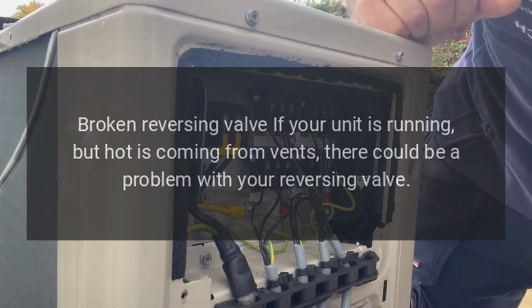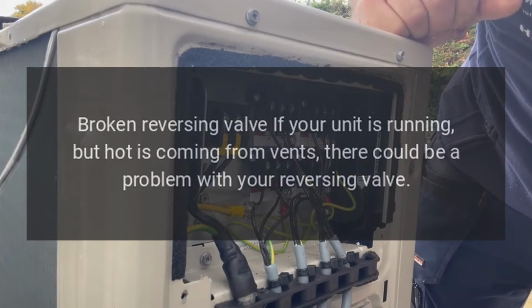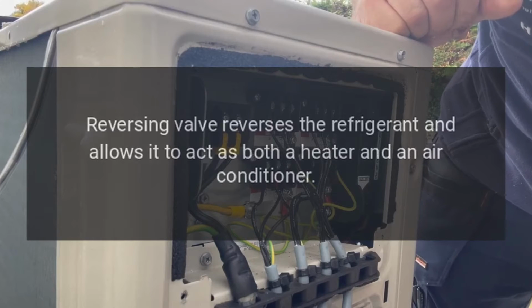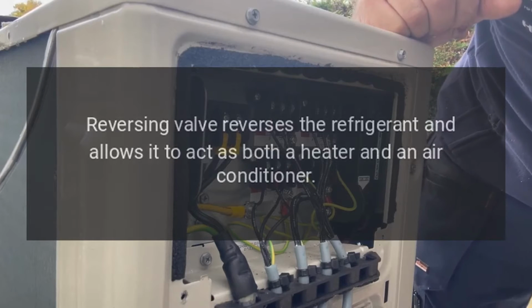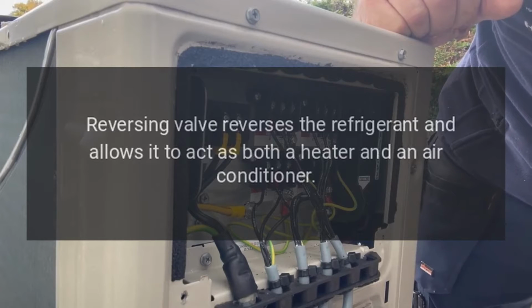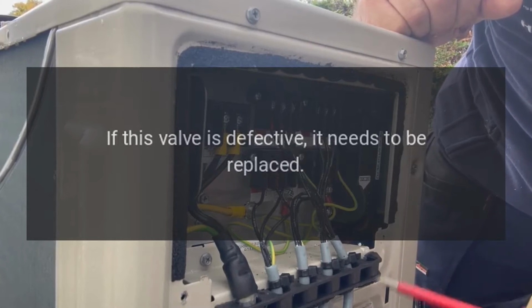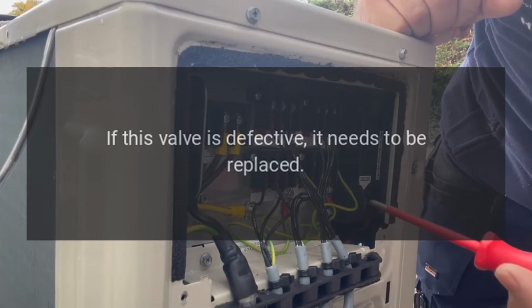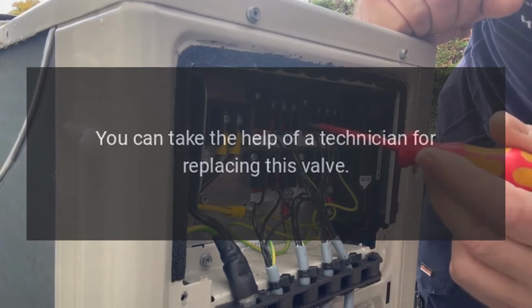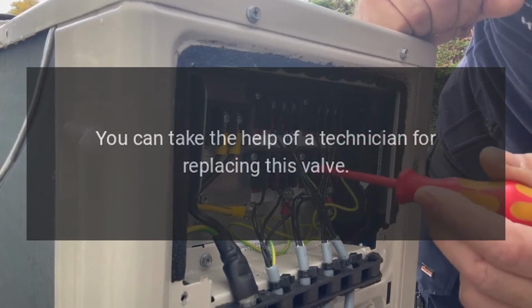Broken reversing valve. If your unit is running, but hot air is coming from the vents, there could be a problem with your reversing valve. The reversing valve reverses the refrigerant and allows it to act as both a heater and an air conditioner. If this valve is defective, it needs to be replaced. You can take the help of a technician for replacing this valve.